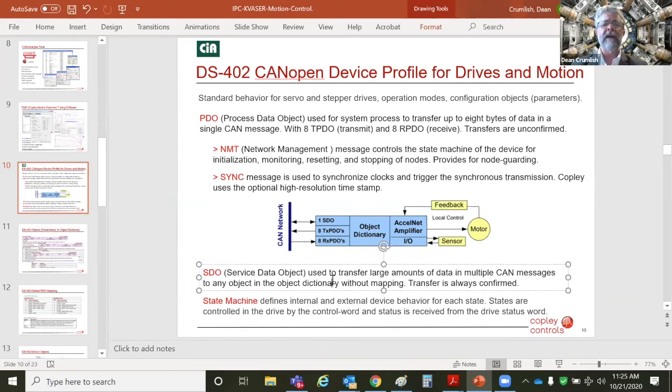SDO, service data object, is for handling large amounts of data, like loading all the parameters for the drive using a CCD file or FOC file over CAN. SDO methods are used. It's a confirming message format. And by the way, if you used up all your mapped PDOs and you need to send or get more data, you can always use an SDO method, even from our CME software, to read and write anything. And of course, there's the state machine.